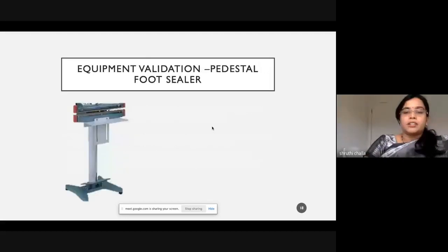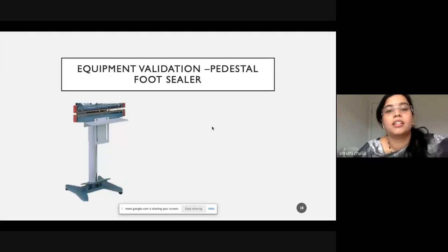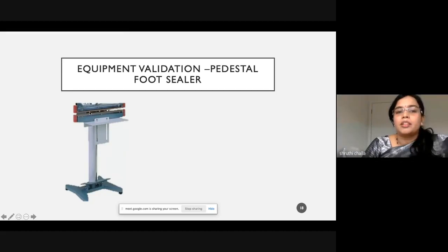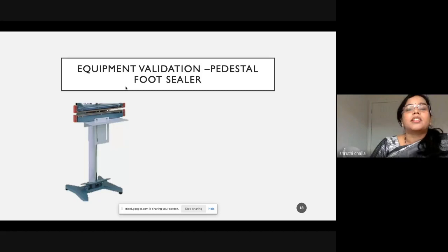We'll look at an example now. To have an easier understanding, I have taken a pedestal foot sealer. This is a very simple equipment. It is a heat sealer where we put packaging in between these 2 jaws and we hit the pedestal, and that would clamp both the jaws and seal the packaging. It would have a temperature probe which is calibrated, and it has an operating range, and we can adjust it depending upon the type of packaging we want to seal.